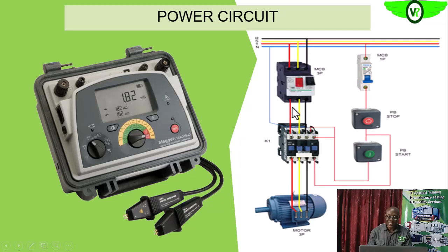So these ones are longer. These are very short runs. Okay, so we can do our test here even when the contactor is open. Okay, so we can run our test here.